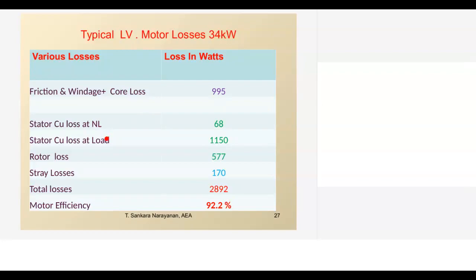Stator copper loss at load, no load, and rotor loss are purely based on the resistance of the motor. So even if the rewinder is changing certain resistance, this loss cannot increase by 20% or 30% because there will be only a marginal variation in the resistance of the winding. Stray loss is just calculated, it is not measured. So some portion of this loss will increase. The major loss increase can come in the iron loss, because whenever rewinding is done, the entire stator gets overheated, or before failure also it can get overheated. During removal of the winding also it gets overheated.